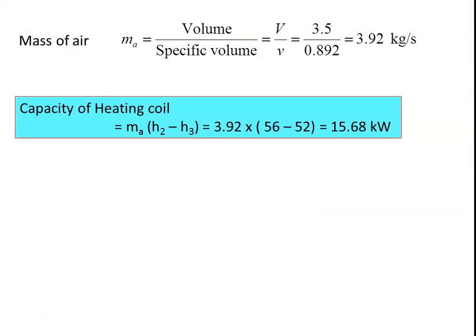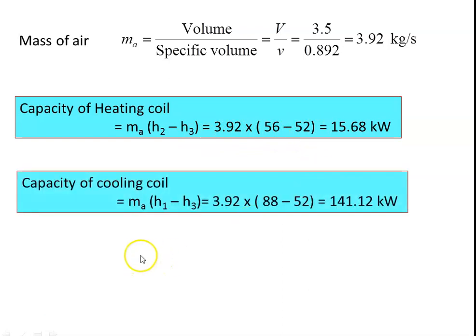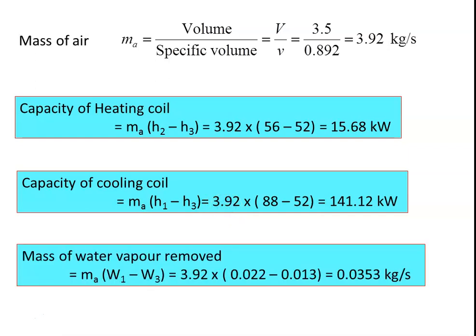Mass of air = volume / specific volume = 3.5 / 0.892 = 3.92 kg/s. Capacity of heating coil = ma × (h2 − h3) = 3.92 × (56 − 52) = 15.68 kilowatts. Capacity of cooling coil = ma × (h1 − h3) = 3.92 × (88 − 52) = 141.12 kilowatts. Mass of water vapor removed = ma × (w1 − w3) = 3.92 × (0.022 − 0.013) = 0.0353 kg/s.